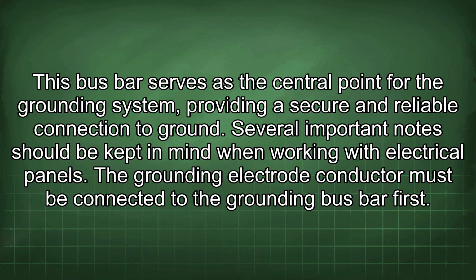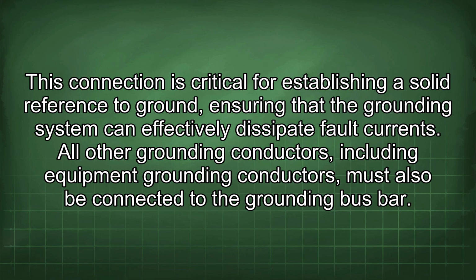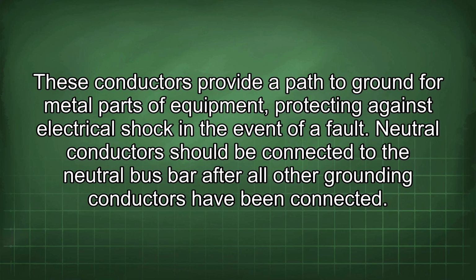The grounding electrode conductor must be connected to the grounding bus bar first. This connection is critical for establishing a solid reference to ground, ensuring that the grounding system can effectively dissipate fault currents. All other grounding conductors, including equipment grounding conductors, must also be connected to the grounding bus bar. These conductors provide a path to ground for metal parts of equipment, protecting against electrical shock in the event of a fault.